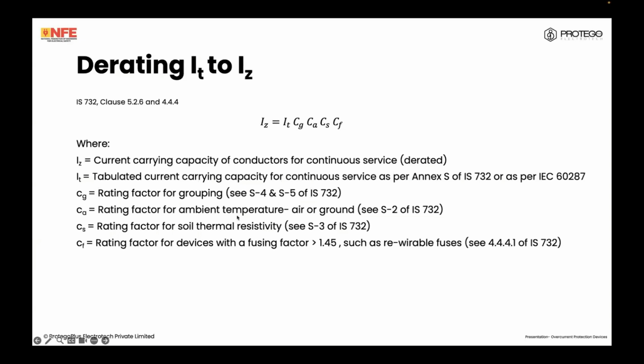The rating factor for ambient temperature. See, these cables, let's say PVC cable, will run at 70 degrees Celsius maximum operating temperature. And let's say the ambient is 30 degrees normally. So it can rise by 40 degrees. However, if the ambient temperature is, say, 45 degrees, then the temperature rise is only 25, 70 minus 45. Therefore, derating is required. If you bury the cable in soil, the soil's thermal resistivity will also affect the ability of the cable to carry heat.